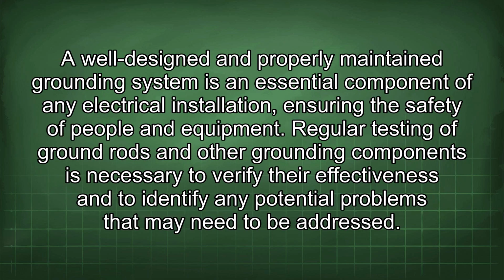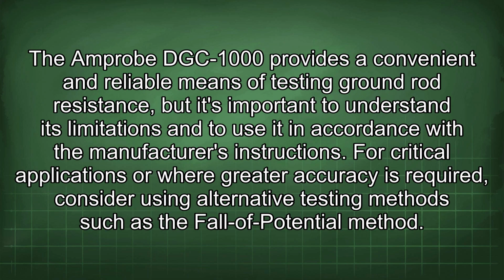A well-designed and properly maintained grounding system is an essential component of any electrical installation, ensuring the safety of people and equipment. Regular testing of ground rods and other grounding components is necessary to verify their effectiveness and to identify any potential problems that may need to be addressed. The Amprobe DGC-1000 provides a convenient and reliable means of testing ground rod resistance, but it's important to understand its limitations and to use it in accordance with the manufacturer's instructions.